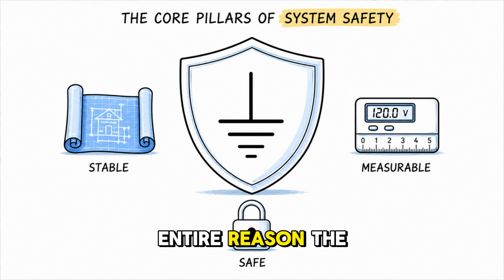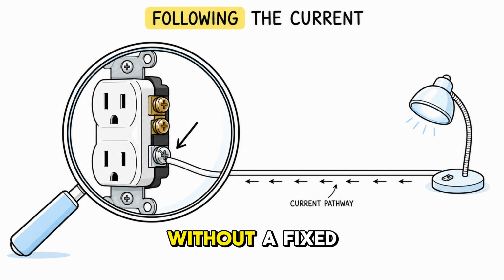This is the entire reason the neutral wire exists. It is the earth-referenced return path that makes AC power delivery stable, measurable, and safe to engineer around. Without a fixed neutral reference point, you could not design a socket, a circuit breaker, or any protection device reliably. But what does the neutral actually do inside your home right now? Let us follow the current.